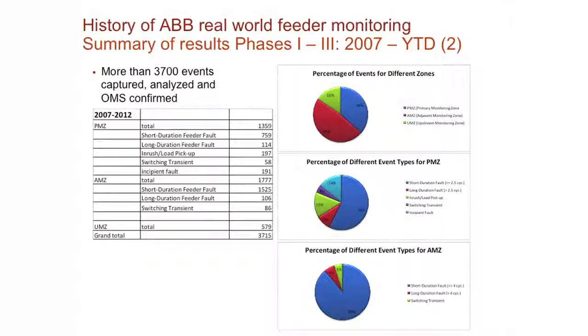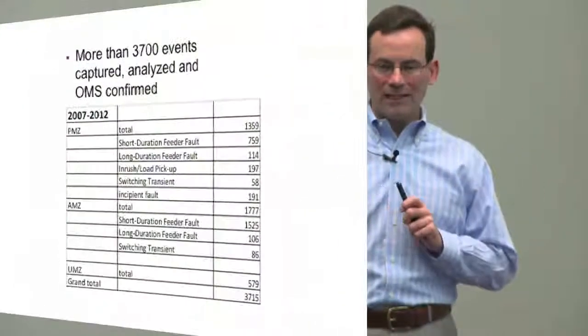What we had was more than 3,700 events captured, analyzed, and then confirmed by OMS. Now, there are a lot of them that were not confirmed by OMS, and I'll talk about that, but you'll see it's proof positive that it happened. The pictures don't lie, so you'll see that soon. This is a tremendous amount of events. Now, this is not including the outside substation data collection equipment we installed, and also inside the sub a power quality device. The power quality device was recording tens of thousands.